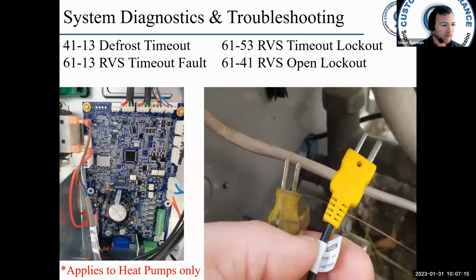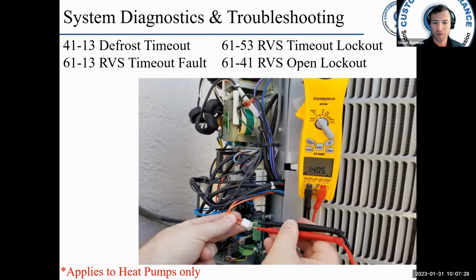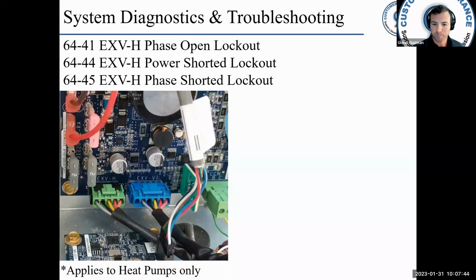We kind of got away from some of the faults here, but 6141 senses that the reversing valve coil is open, or an infinite resistance, and it's not operational. Okay. Ohm the coil. You can see here, ohming the coil. What's it supposed to read? Well, this was a 5-ton unit, give or take 14 ohms, plus or minus maybe an ohm or two. Okay.